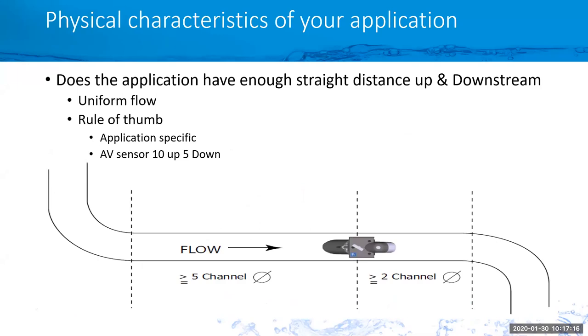Other questions I get are, how much straight run of pipe or channel do I need for installing an area velocity sensor? Well, the biggest thing is you need uniform flow. Because we're taking the velocity reading, and without uniform flow, it's going to be difficult to get accurate flow readings. So the rule of thumb is that, depending on who you ask, we'd like to see at least 10 upstream and 5 down. Other people you ask are going to say 5 up, 2 down.